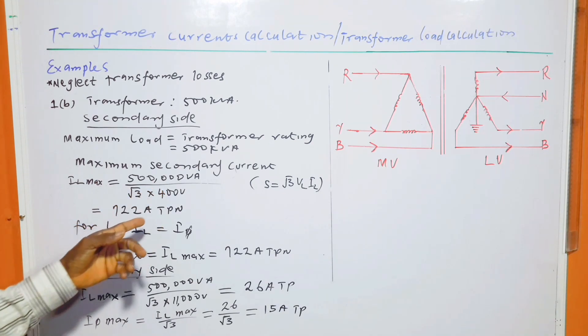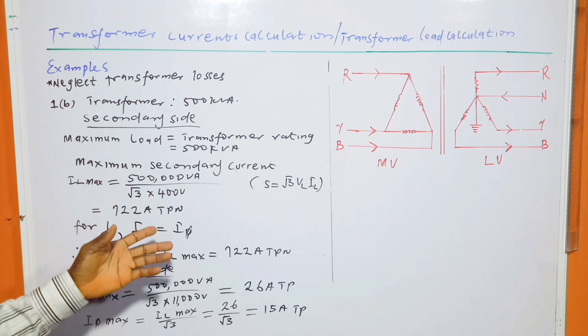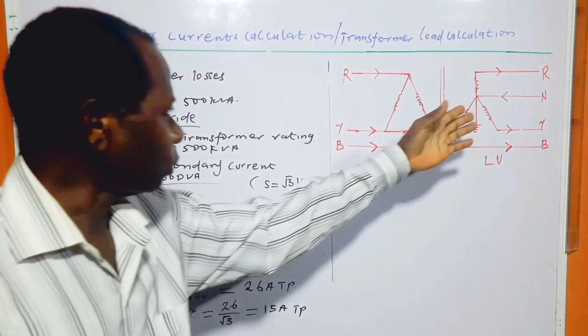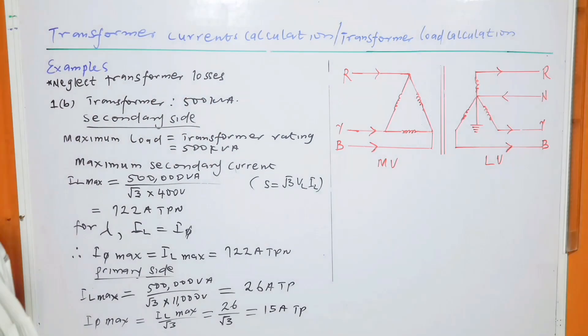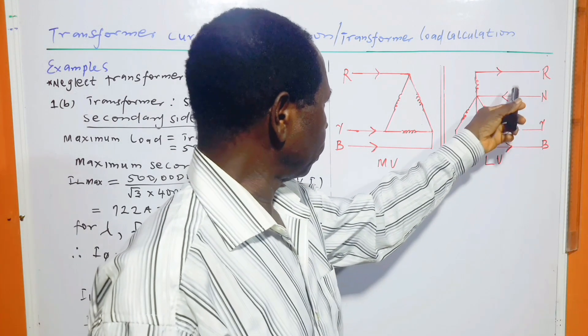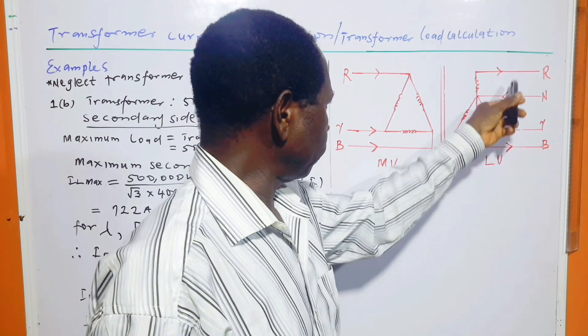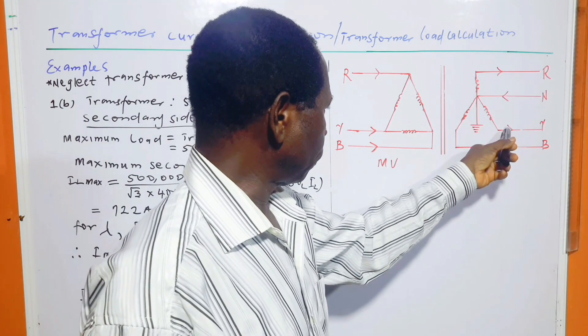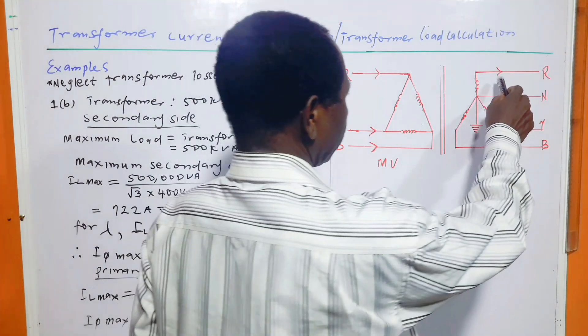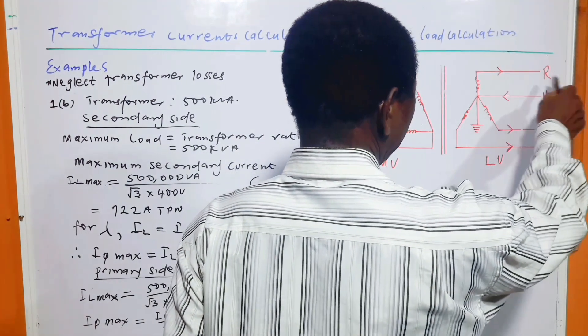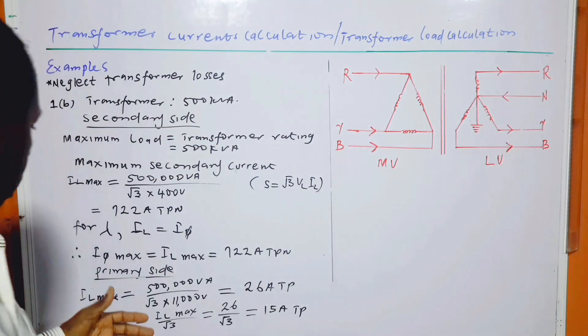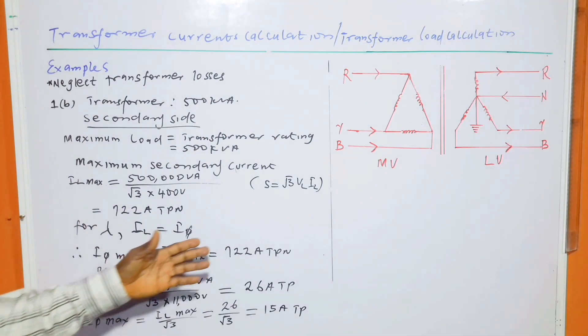From I = S / (√3 × V_line), the maximum secondary line current is 722 amperes, three-phase with neutral. That is the line current — the current flowing into the load from the transformer winding.